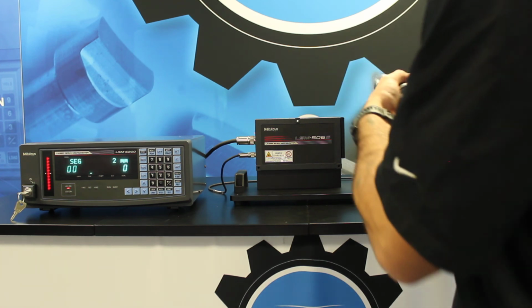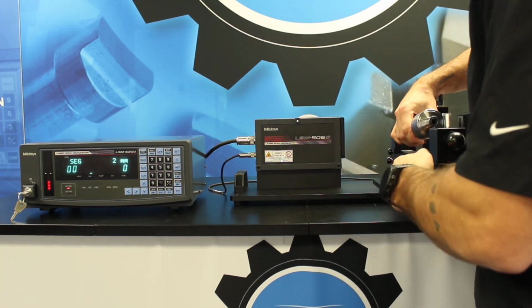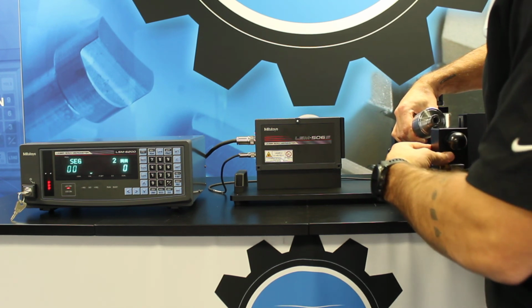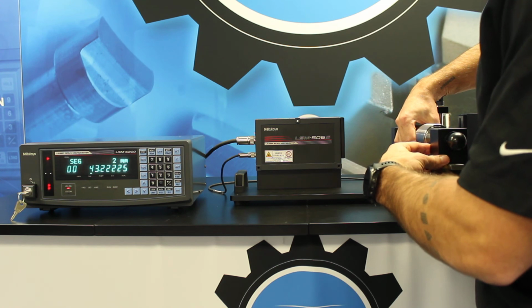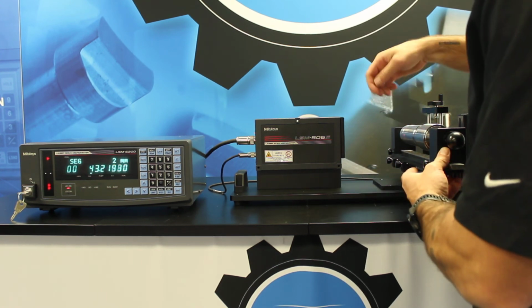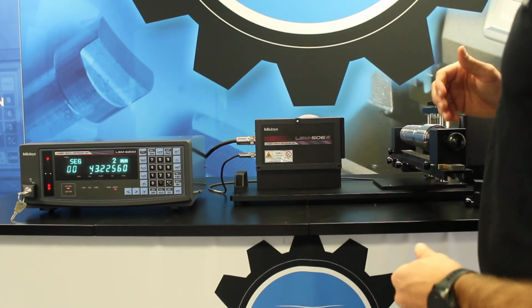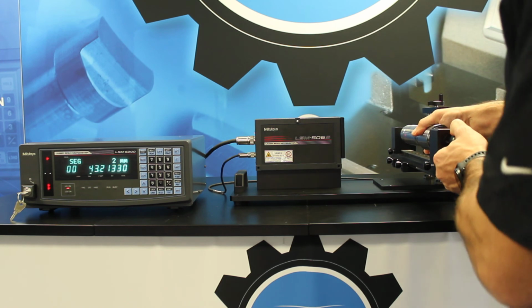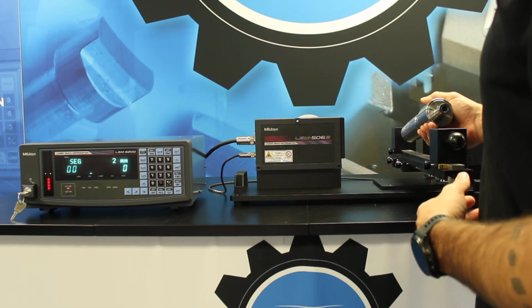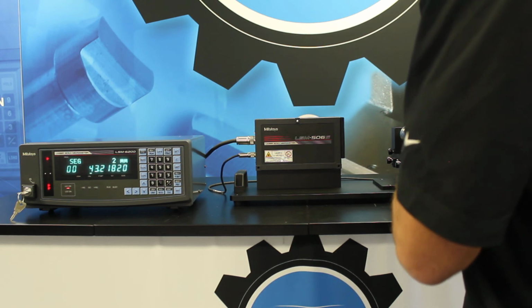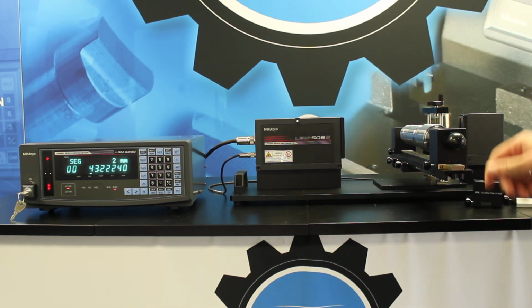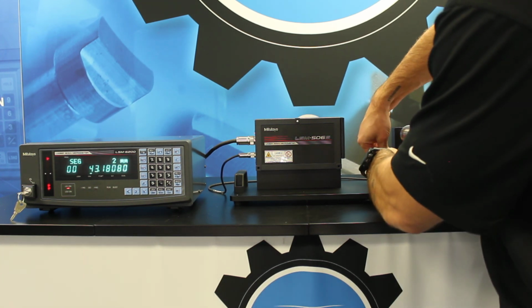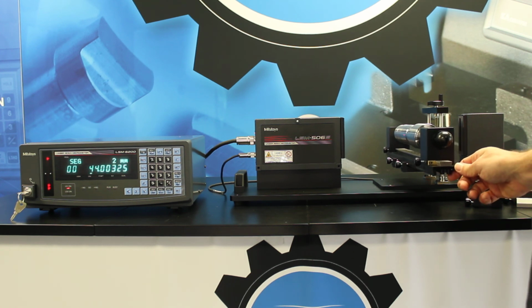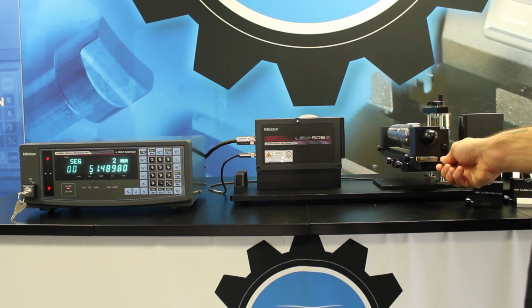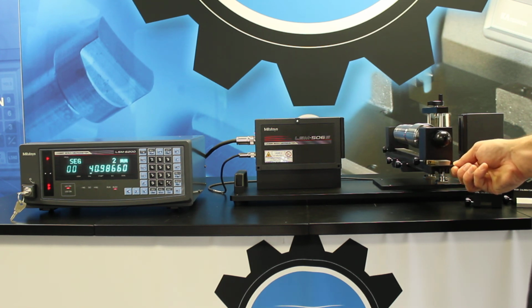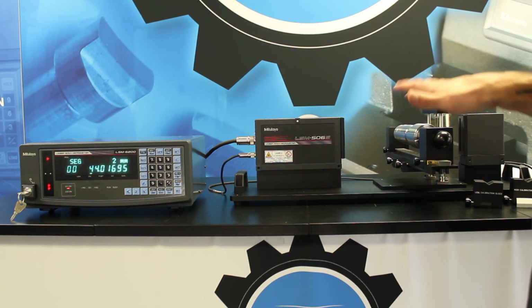Now I'm going to take my part and locate this between the centers here. I do have the thumb screw adjustability for the centers to increase or decrease that distance. And I'm going to get some positive pressure here on the center, lock that thumb screw in place. Now moving forward, I should be able to pull out this spring-loaded center, and that allows me to load and unload the part as I get into my more rapid checks. Now that the part is loaded, I can unlock my thumb screws, and I can now slide this back and forth along those diameters to check the different diameters along the shaft. This was a quick video on how to set up, calibrate, and use a laser scan micrometer.